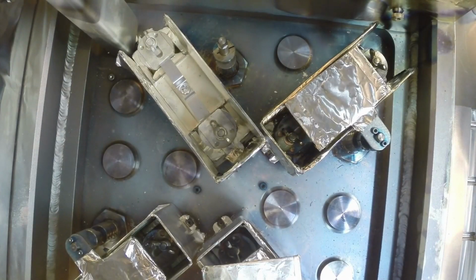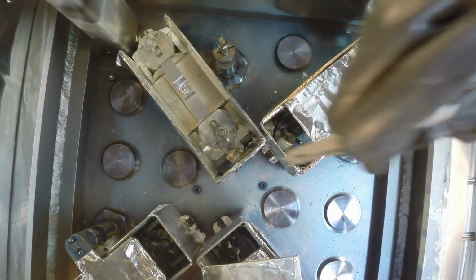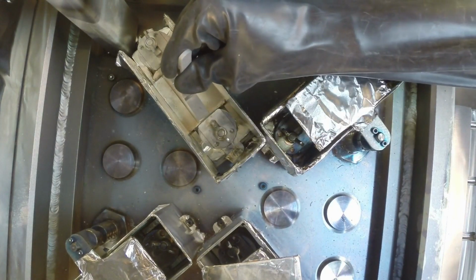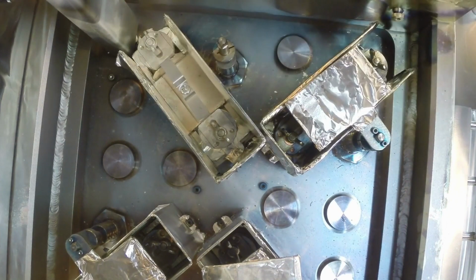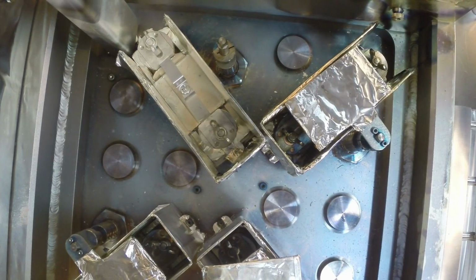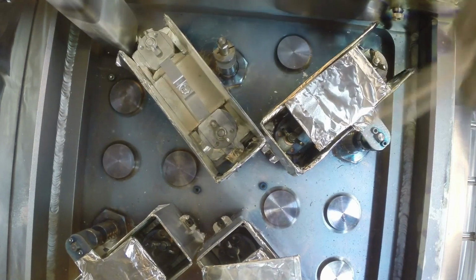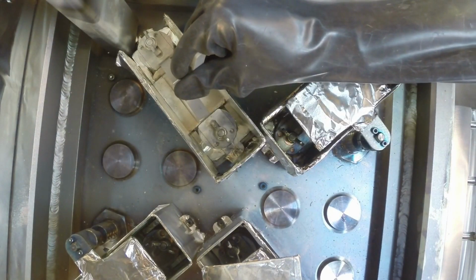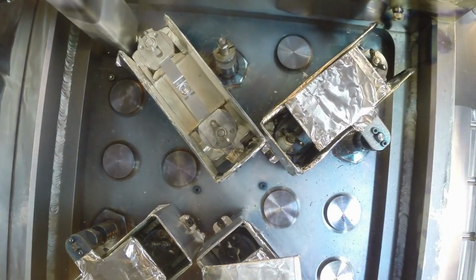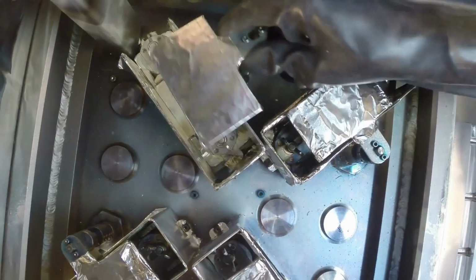Now, we can load silver material onto the boat. In this case, we'll load two silver pellets onto the boat because each silver pellet is good for about 50 to 60 nanometers of silver. After loading the silver pellets, we make sure to install the source shield back into place, and now we can load our substrates.